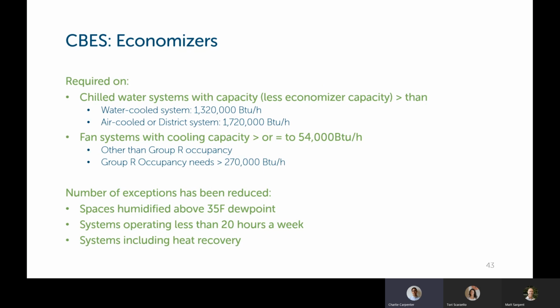And the number of exceptions for this requirement have been reduced from the 2015 code. I've got a couple of them listed here: spaces that need to be humidified above a 35 Fahrenheit dew point, systems operating less than 20 hours per week, or if you have heat recovery ventilation tied in with that system, then it does not need an economizer.